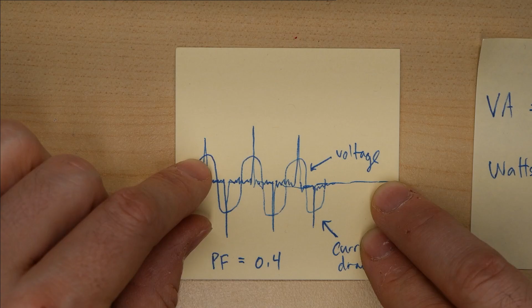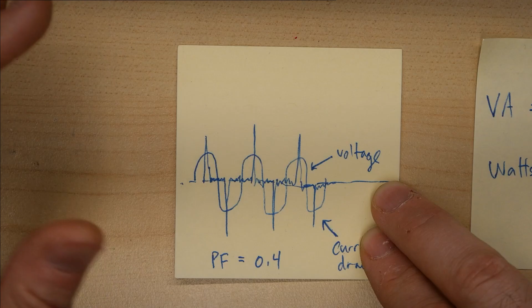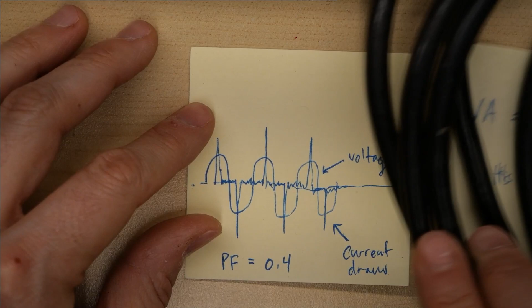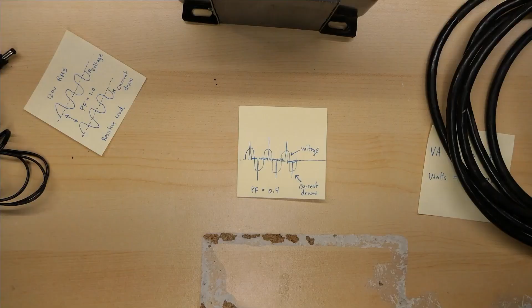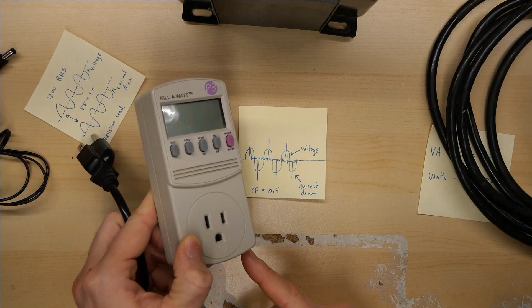If we measure 1 amp as an average, the fact that it's spiking way up and then there's nothing means it could actually be drawing 2, 3, 4 amps during these spikes. The transformer and line cords connecting it have to handle those current draws. A device like a Kill A Watt, which is pretty commonly available, can measure watts, amps, volts, and also show you the power factor.